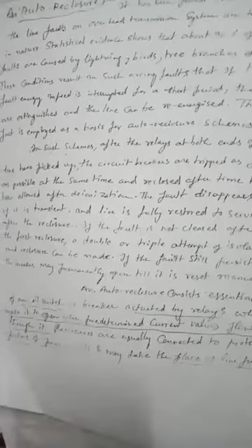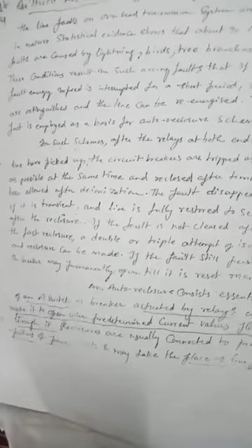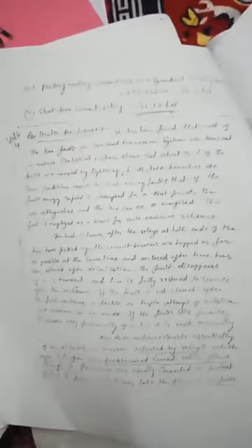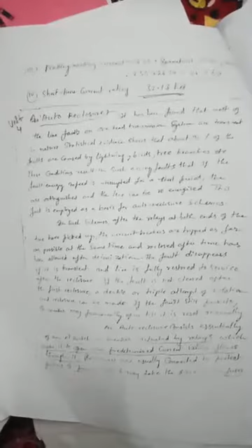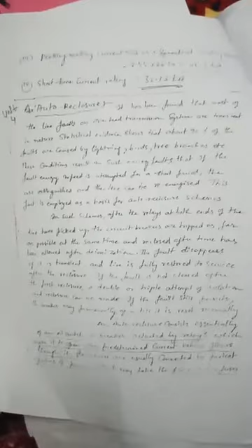Next, briefly discuss about auto reclosure. Give a brief note about auto reclosure. Most of the line faults on overhead transmission line systems are transient in nature. Statistical evidence shows that about 90% of the faults are caused by lightning, birds, tree branches, etc. This condition results in arcing faults, such that if the fault is interrupted for a short period, the arc extinguishes and the line can be re-energized. This fact is employed as the basis for the auto reclosure scheme.